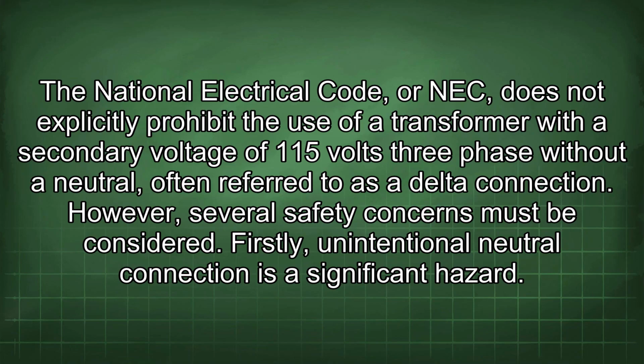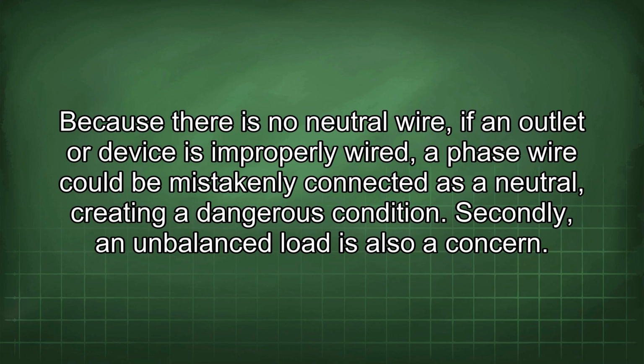The National Electrical Code, or NEC, does not explicitly prohibit the use of a transformer with a secondary voltage of 115 volts three-phase without a neutral, often referred to as a delta connection. However, several safety concerns must be considered. Firstly, unintentional neutral connection is a significant hazard. Because there is no neutral wire, if an outlet or device is improperly wired, a phase wire could be mistakenly connected as a neutral, creating a dangerous condition.